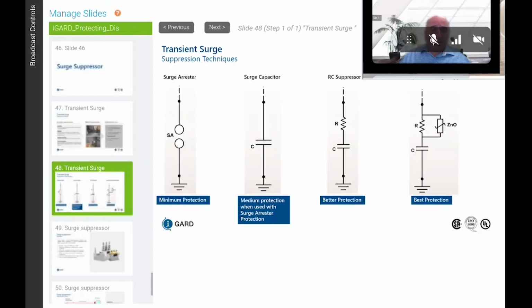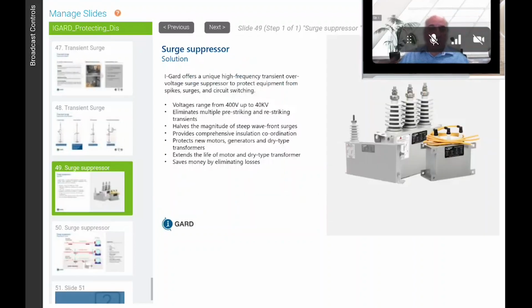So we can have surge arresters, which provide minimal protection for surges, surge capacitors, surge RC snubbers, or surge snubbers. The difference is that the surge arrester requires a long-term overvoltage. You have to exceed the MCOV before it operates. The surge suppressor reacts specifically to very fast transients and shorts to ground. These particular devices range from 400 volts to 40 kV.